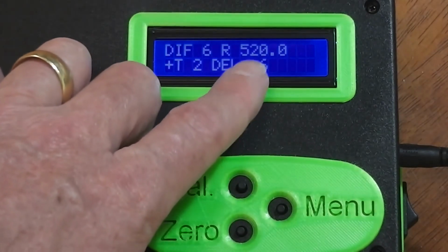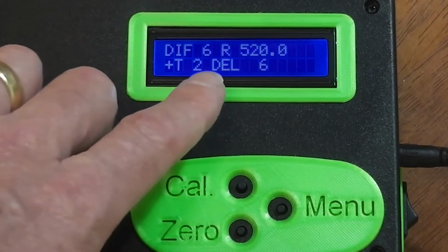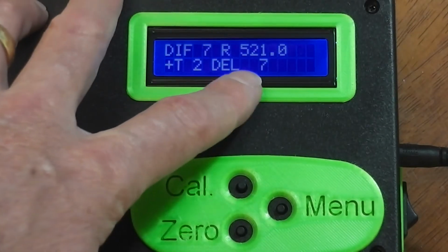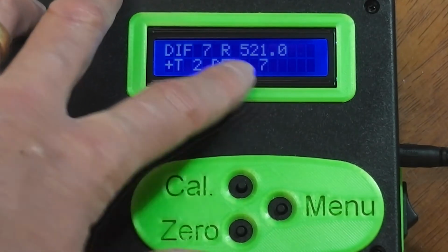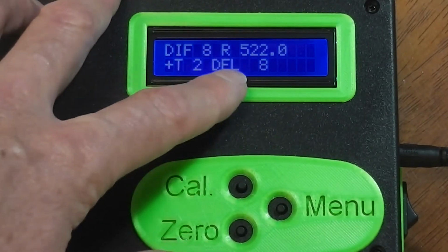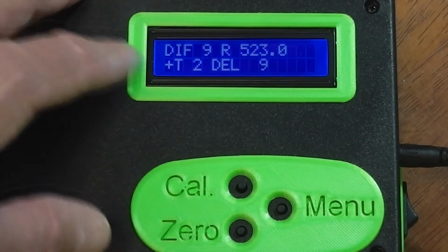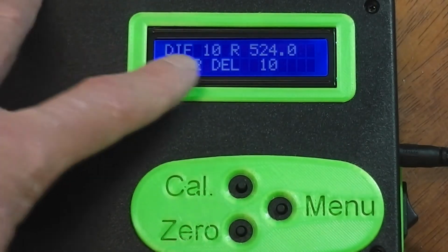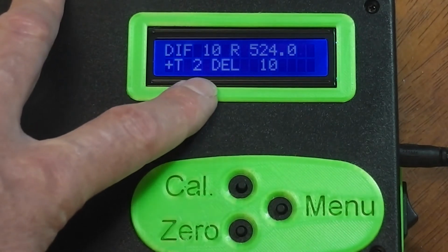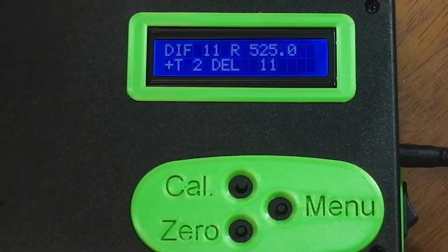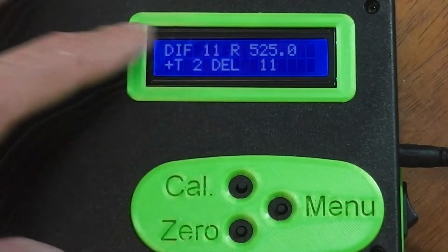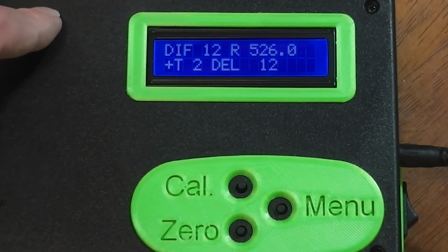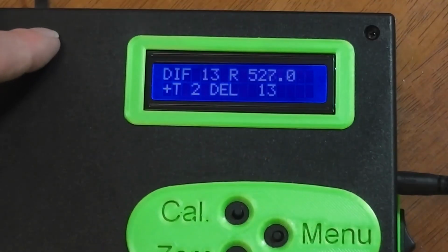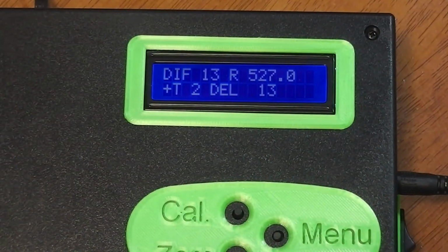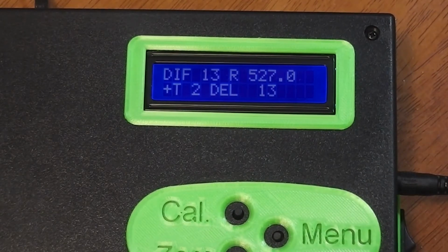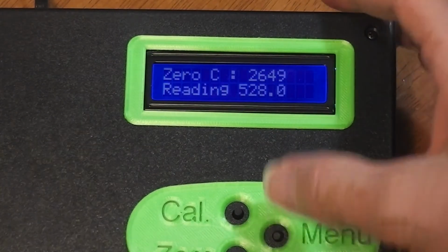Now you'll notice that the reading itself is actually climbing up from that value, and you can see that the difference from where it was calibrated at is 7, and the difference overall is the same, is going up together. Now the reason it's going up is because the heater's on and the unit's warming up. And so even just the heat change on the inside can create quite a significant variation on it. But while that's doing that, we'll go through the menu and we'll have a look at some of the menu items. Now, so we press the menu, it takes us in here.